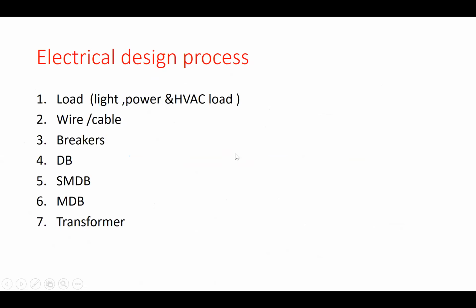If you follow any process through these 7 steps, you can understand any project. First, what is the load - light, power, wattage. Based upon the load you calculate the breaker sizes and cable sizes. Based upon these inputs, you design the DB enclosure - how many breakers are inside the DB. Once you know the breakers, you know the isolator rating. After that, based upon the DBs, you design the SMDBs, and SMDB to MDB to transformer - this is basically the electrical engineer's job, from load to transformer. These 7 steps complete your project.